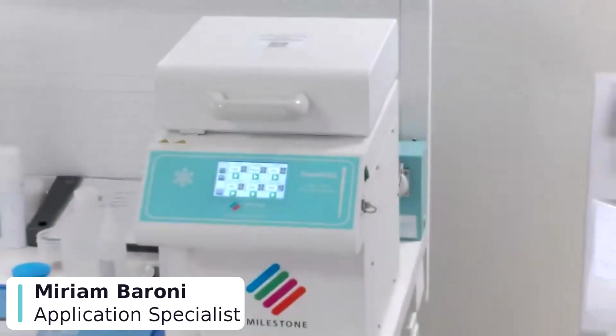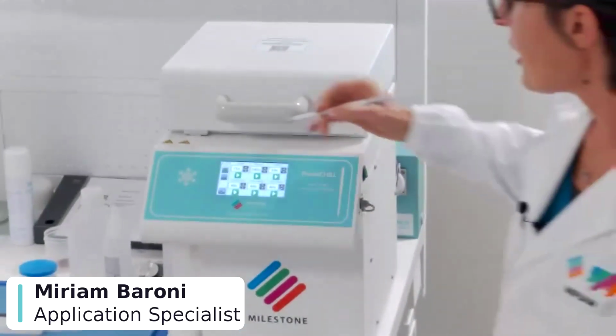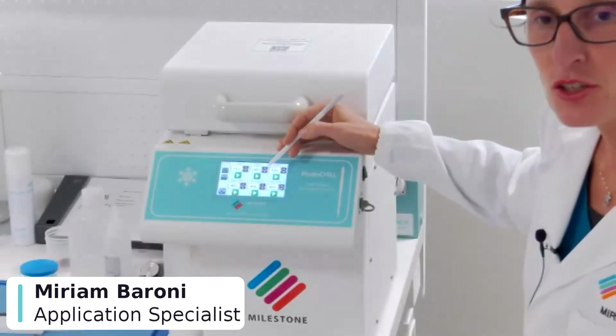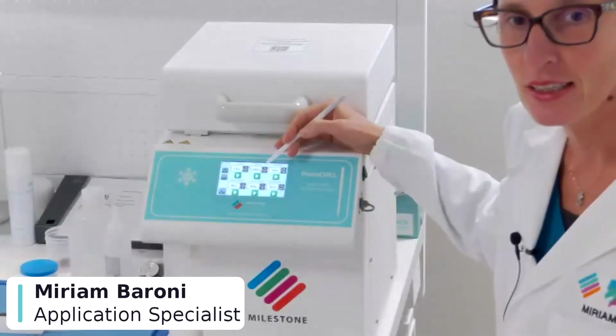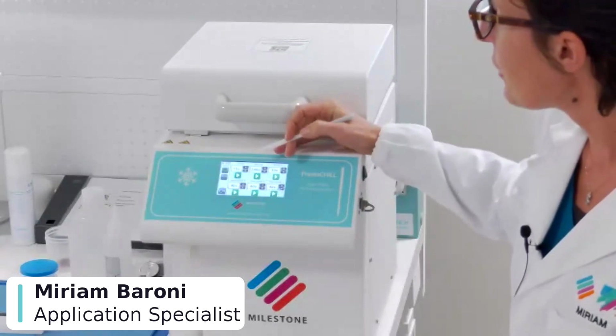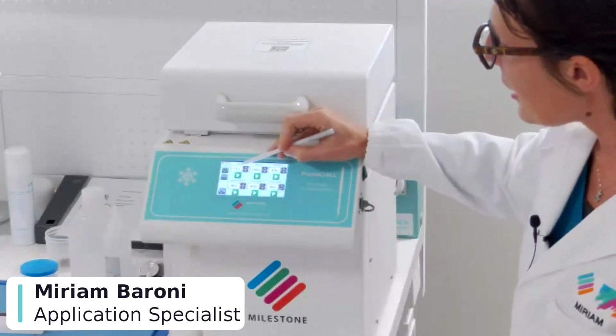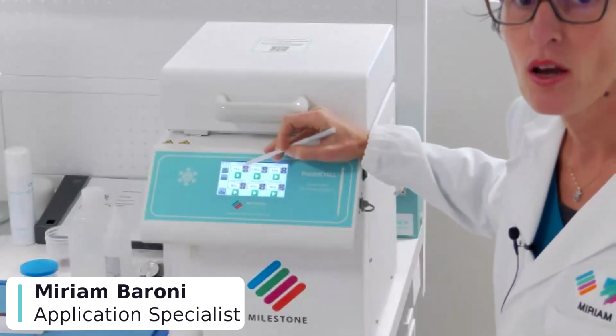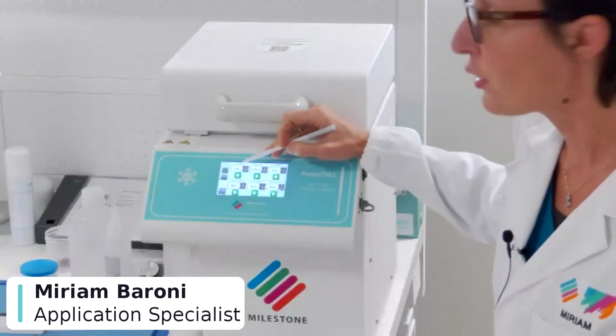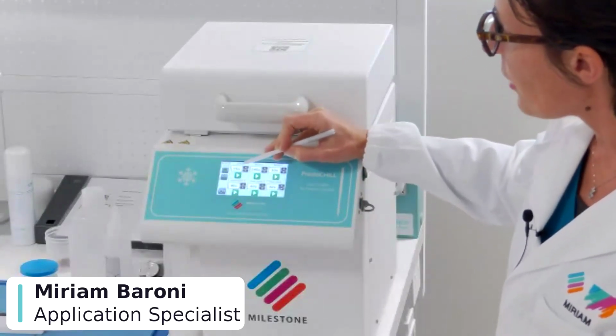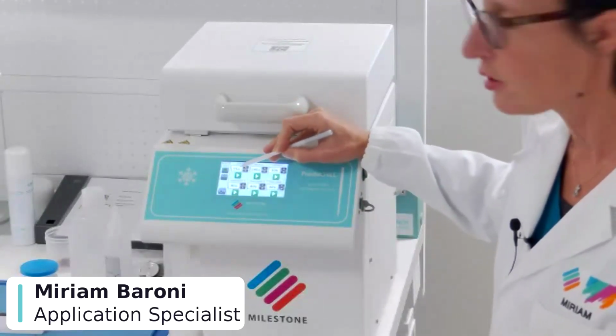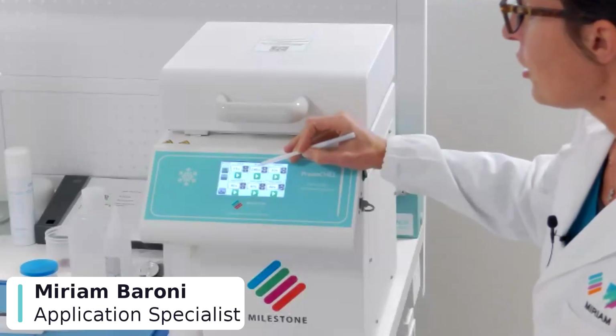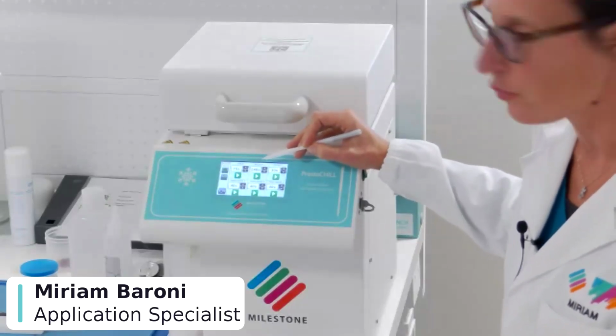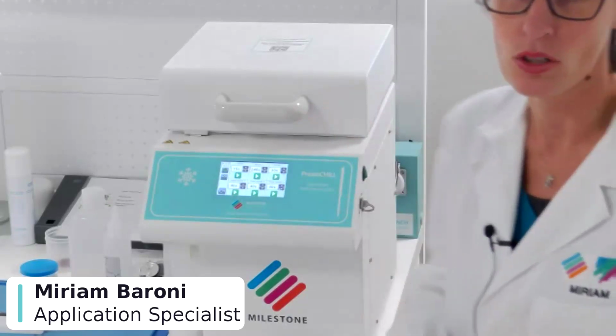I'm sorry that I can't show you very well the image. Oh, maybe now. Okay, so we have this page in which we have 6 different timers, and we can set up the name and the perfect freezing time for each tissue type. So for example, here in my lab for brain, I freeze only 15 seconds. For breast, I do 240 seconds, so 4 minutes, and for kidney, 30 seconds.